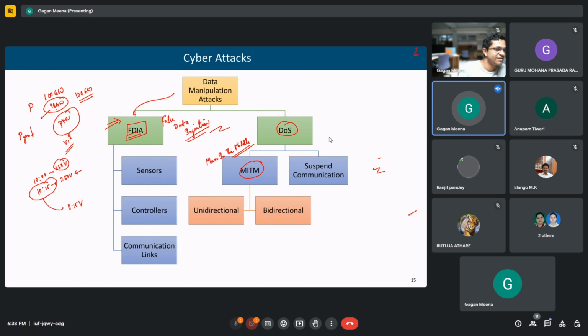False data is saying that the load is reducing. Earlier it was 100 gigawatts; now it is saying the load has reduced, but actually it has not. So as per the false data, the generation should also reduce, because we want to maintain the frequency -- if overall load is 98 gigawatts, the generation should also be close to it, correct? But actual demand is 100 gigawatts, and if I make the generation 98 gigawatts, there is a mismatch, and frequency will deviate.